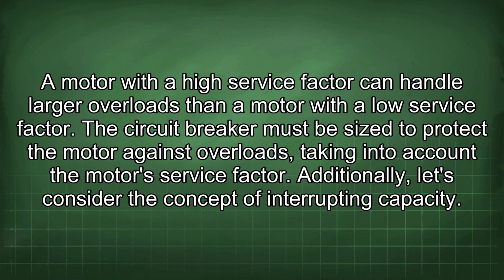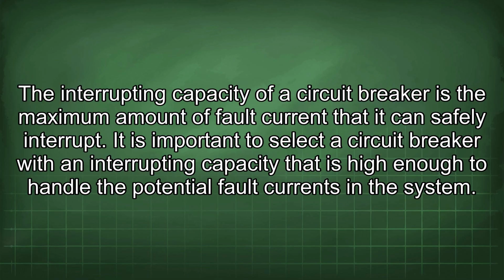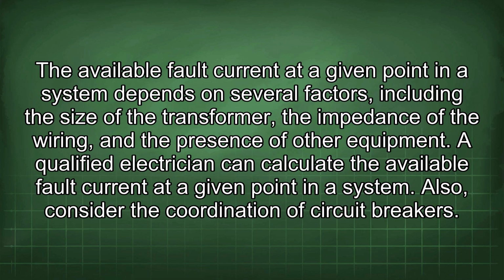Additionally, let's consider the concept of interrupting capacity. The interrupting capacity of a circuit breaker is the maximum amount of fault current that it can safely interrupt. It is important to select a circuit breaker with an interrupting capacity that is high enough to handle the potential fault currents in the system. The available fault current at a given point in a system depends on several factors, including the size of the transformer, the impedance of the wiring, and the presence of other equipment. A qualified electrician can calculate the available fault current at a given point in a system.